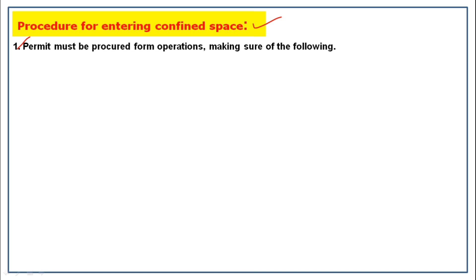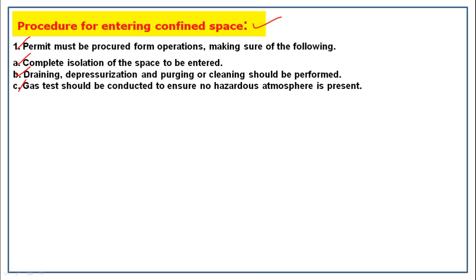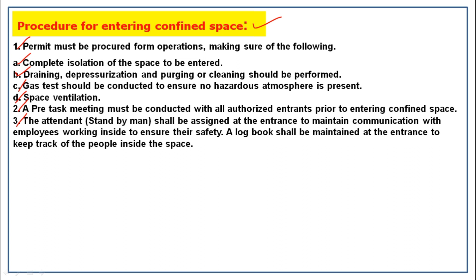Procedure for entering confined space. A permit must be procured from operations, making sure of the following: complete isolation of the space to be entered, draining, depressurization and purging or cleaning should be performed, a gas test should be conducted to ensure no hazardous atmosphere is present, and space ventilation. A pre-task meeting must be conducted with all authorized entrants prior to entering confined space. The attendant standby man shall be assigned at the entrance to maintain communication with employees working inside to ensure their safety. A logbook shall be maintained at the entrance to keep track of the people inside the space.